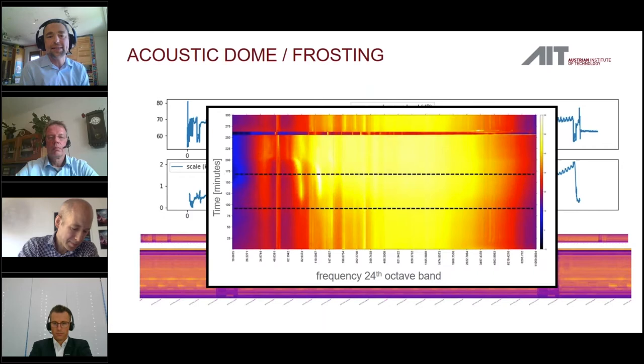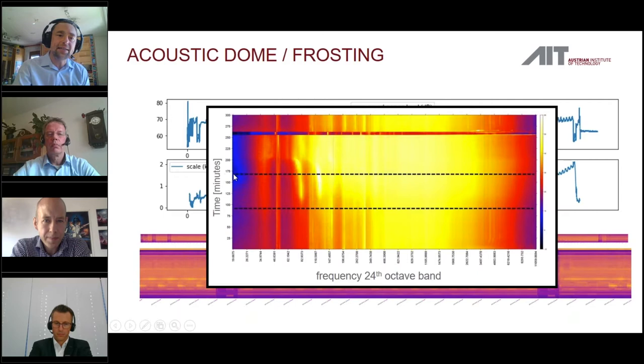I can show you this in detail. Here you have the frequency on the x-axis, these are the typical frequency bands, and on the y-axis you have the time. What you see here is that in a range of, let's say, 80 minutes to 180 minutes, so 100 minutes, is the area of frosting. It's not only that the whole heat pump gets a bit louder, it's also that several frequency bands are excited which are not there before.